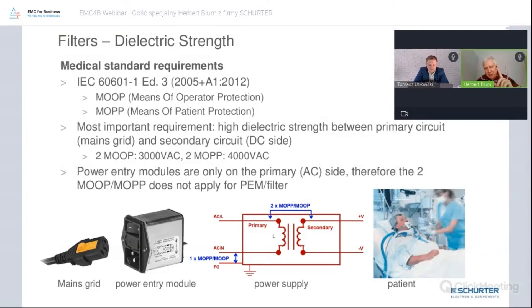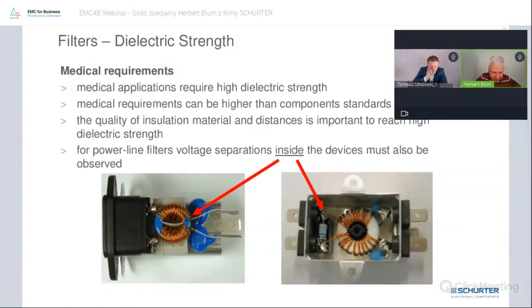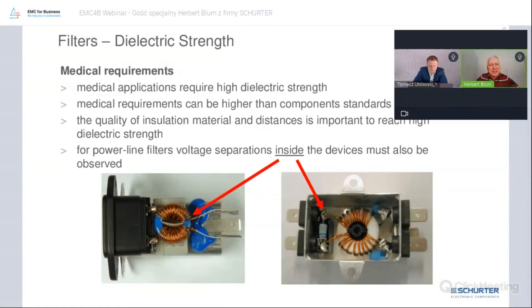On the secondary side of the power supply, which may be connected to a patient, we also guarantee the creepage and clearance distance inside the filter in the filter design.